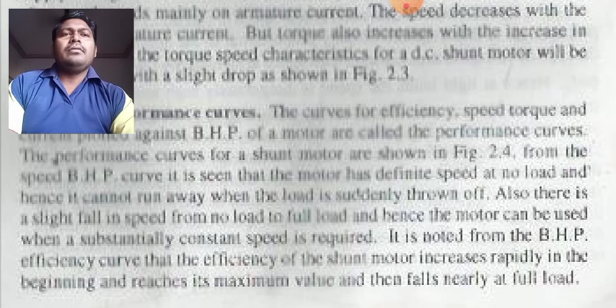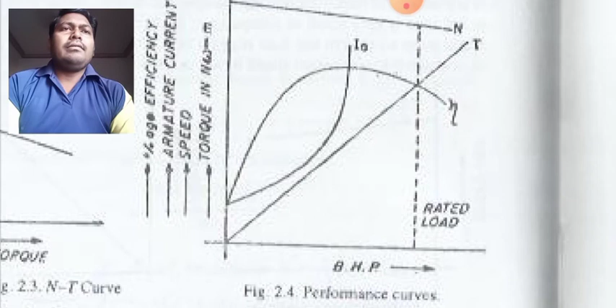It is noted from the BHP efficiency curve that the efficiency of the shunt motor increases rapidly in the beginning, reaches its maximum value, and then falls nearly at full load. So in this performance curve, you can check this diagram. This is the performance curve. It shows you the efficiency graph. It also shows you the torque, armature current and the speed.